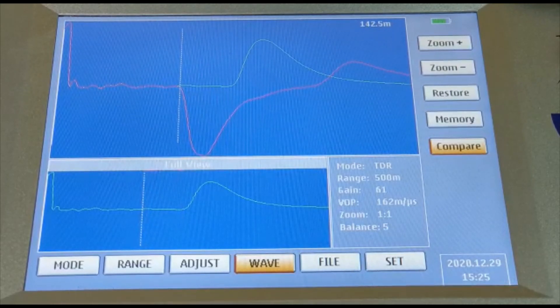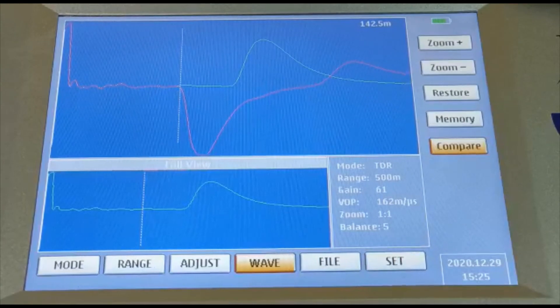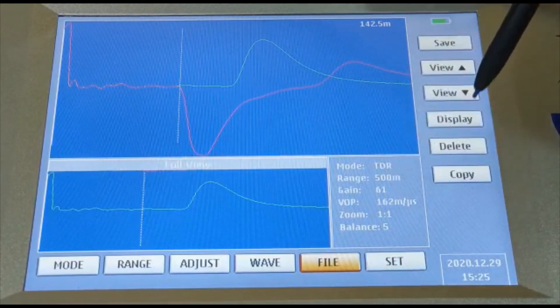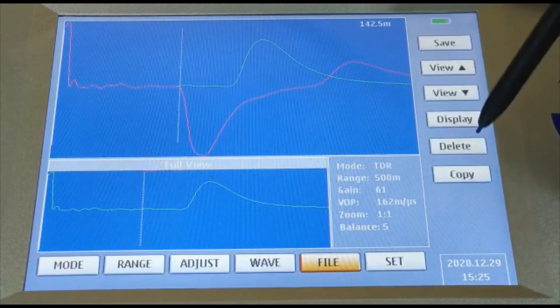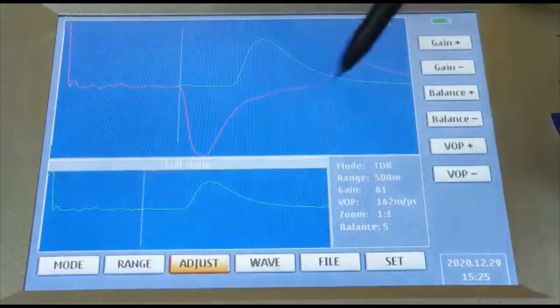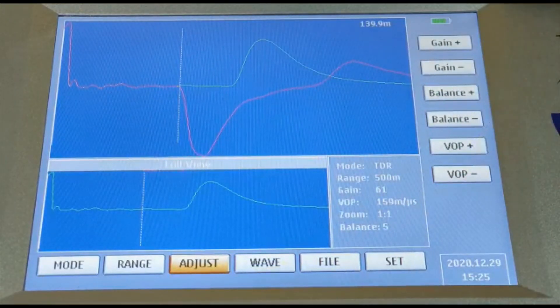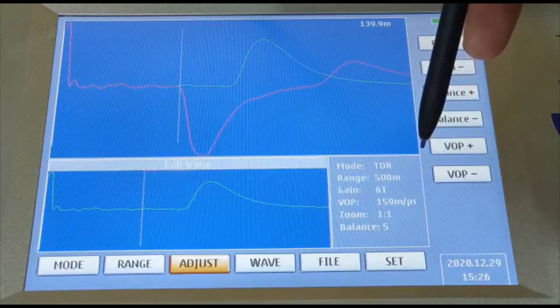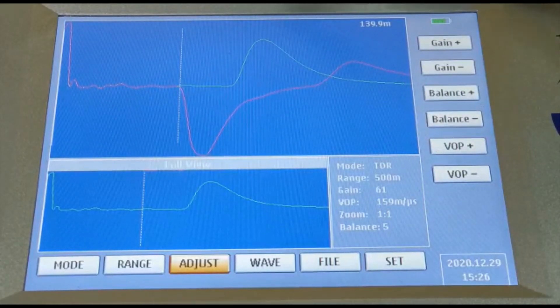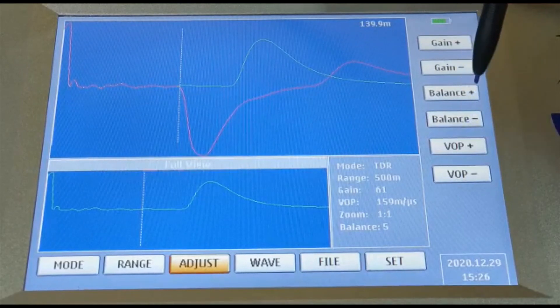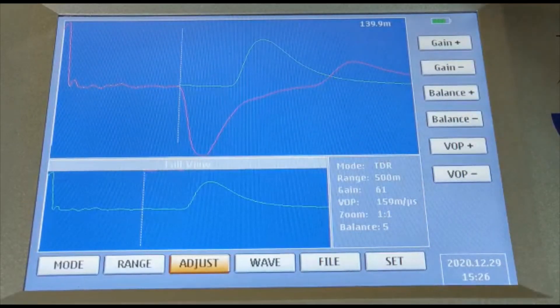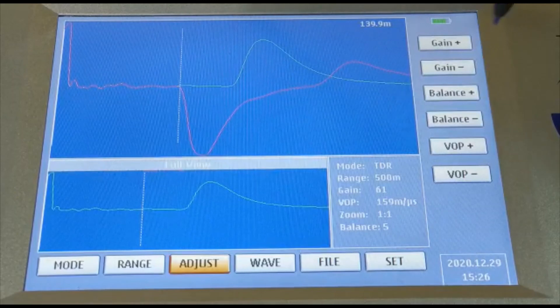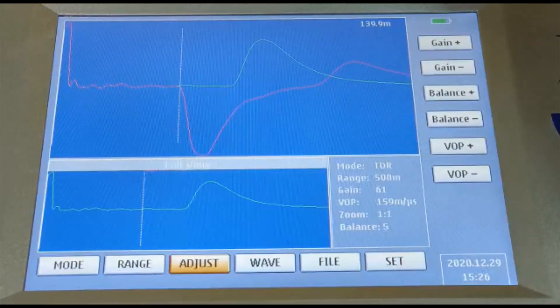You can rotate the cursor and see that the fault is at approximately 142.5 meters. With VOP set to 159, you can see that the distance reads 139 meters accurately. If you don't set the proper VOP, you need to account for a plus or minus error in the distance. If you know your VOP exactly, it will accurately locate you to the precise fault location. I hope you now have clear information about the equipment and how to use it — thank you very much.